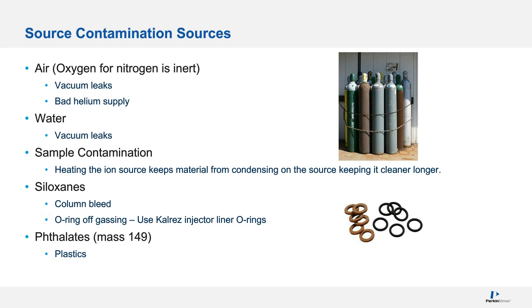Again, source contamination sources. Air is good for us, but it's not good for the mass spec. And it's not the nitrogen in the air, it's the oxygen. Nitrogen is inert. Oxygen oxidizes. Remember, people go out partying on the weekend and wake up Monday morning and fill cylinders. Everybody makes mistakes. I make them every day. So we could get a bad supply of helium. Most people will use filters because this can really contaminate a system. And filters protect. I know my service engineers, they cringe if people don't use filters. So it really can save them being down from getting a bad tank. Although, these gas manufacturers are very good, it's very rare to get a bad tank. But it could happen.